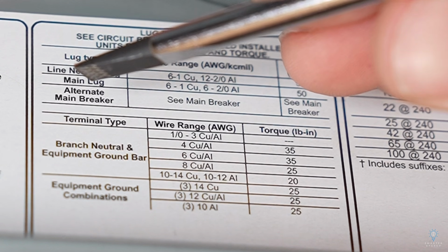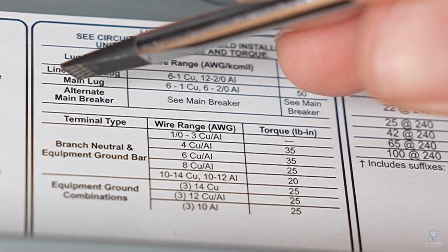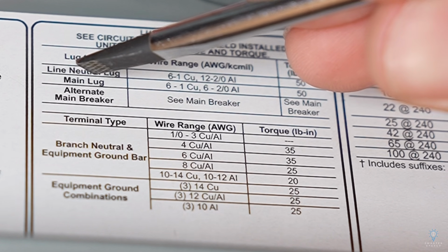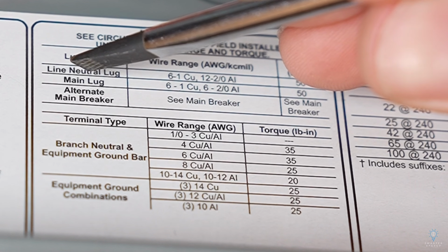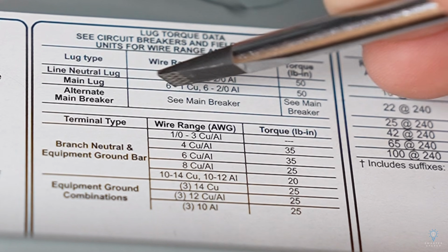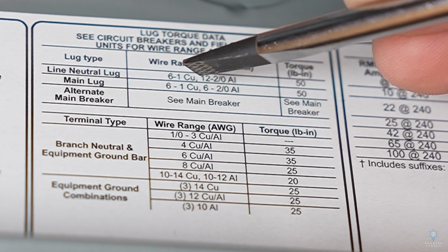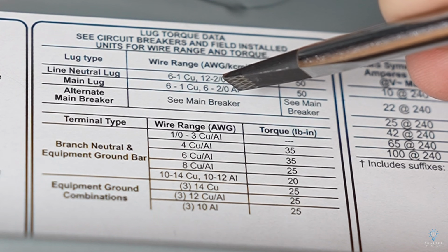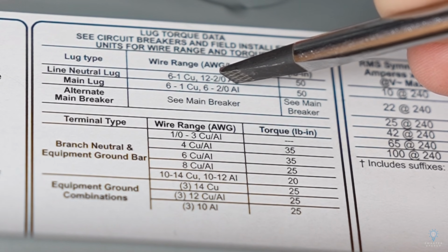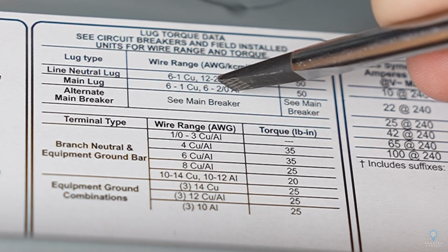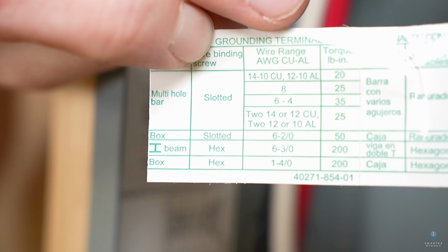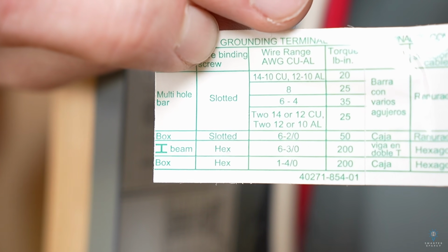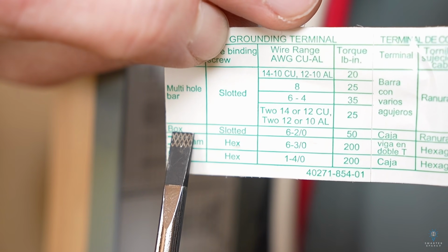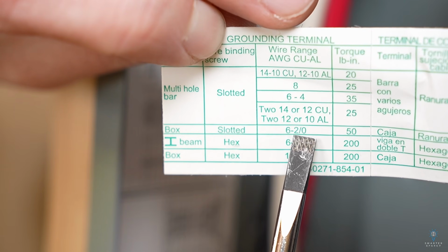The second one here though says main lug. So these would be the two lines. So line neutral lug, that's going to be that big lug for the neutral. Then the main lug is actually 6 gauge to 1 gauge copper or 6 gauge to 2/0 gauge aluminum. So those would be the two main lugs that we landed that black and red wire on. And then if we take a look at this sticker that came with the ground terminals, we will see that the box terminal is 6 gauge to 2/0 gauge.